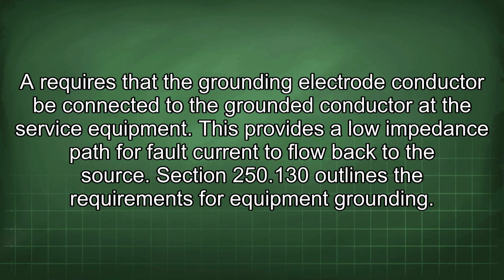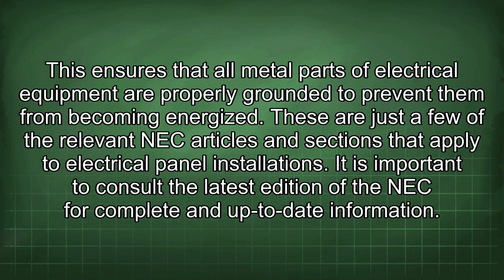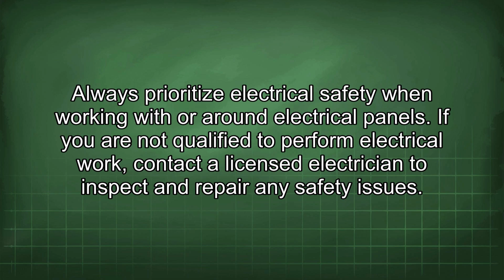Section 250.130 outlines the requirements for equipment grounding. This ensures that all metal parts of electrical equipment are properly grounded to prevent them from becoming energized. These are just a few of the relevant NEC articles and sections that apply to electrical panel installations. It is important to consult the latest edition of the NEC for complete and up-to-date information. Always prioritize electrical safety when working with or around electrical panels. If you are not qualified to perform electrical work, contact a licensed electrician to inspect and repair any safety issues.